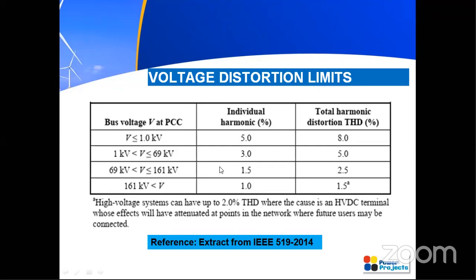Once you are going to integrate your wind farms with the grid, you have to be very careful about the voltage distortion limits. And one important thing is that it is to be seen at the point of common coupling. So you need not check the harmonics at all the points. It is sufficient to check the THD limit at the point of common coupling. That's what IEEE 519 says.